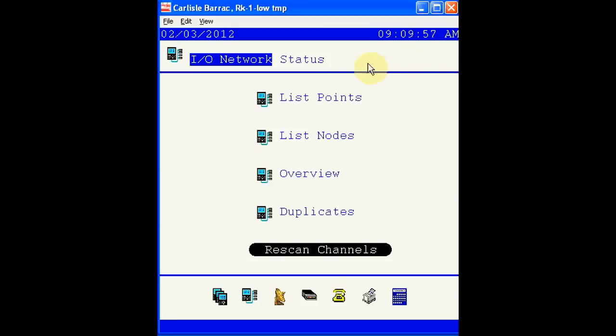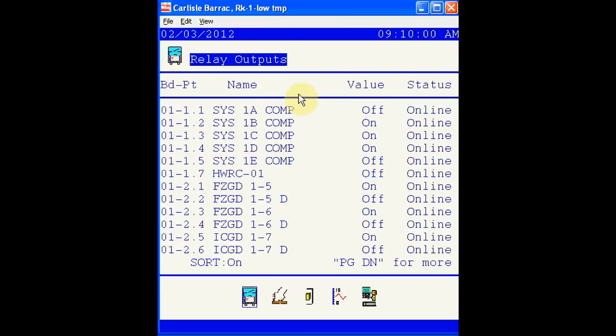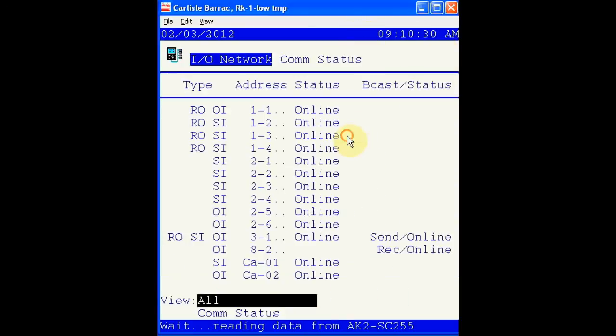Let's take a look at list points. Here you see a list of all points in order by board point. We know they're in order by board point because the sort function is turned on. Currently we're looking at relay outputs, but we could switch to sensor inputs, on-off inputs, variable outputs, or other controllers, which could include rooftop controllers such as RTCs. List nodes will list the status of boards online on this 255. As you can see, all boards are currently online.